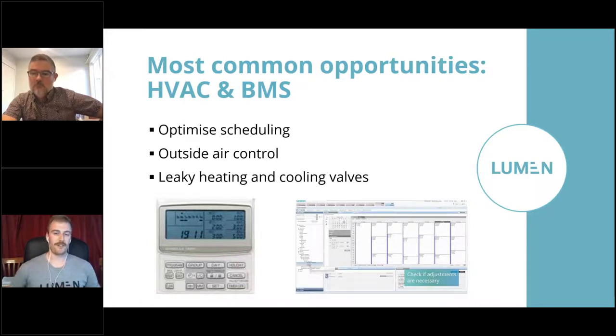Optimizing outside air control and fixing leaky heating and cooling valves can save 10, 20, even 30% of building energy consumption. And the costs should be included in your maintenance budget, but we're only talking a few thousand dollars often. I've got a really good example on the next slide.